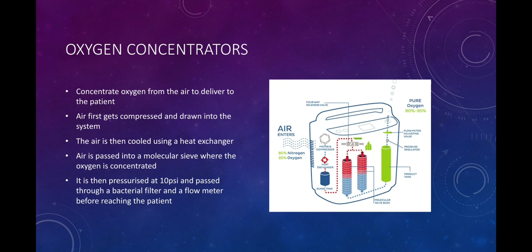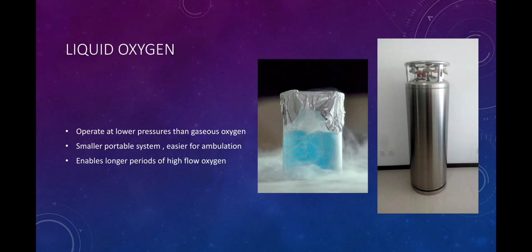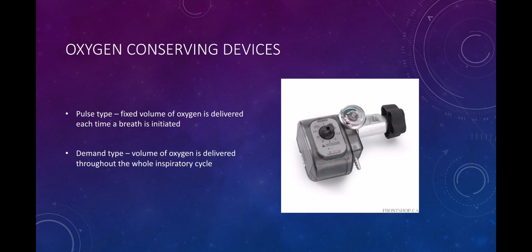This is liquid oxygen, which operates at lower pressure than gaseous oxygen. It is a smaller and portable system, easier for ambulation, and enables longer periods of high flow oxygen. Oxygen conserving devices: pulse type, where a fixed volume of oxygen is delivered each time a breath is initiated. Demand type, where the volume of oxygen is delivered throughout the whole inspiratory cycle.